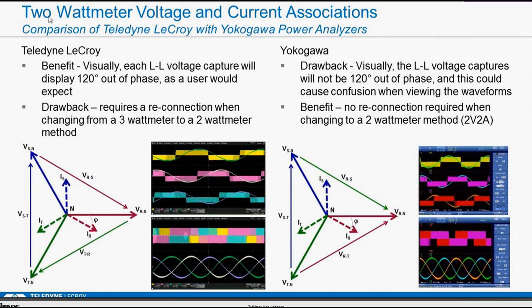One thing that gets confusing is, and this isn't bad, it's just the way it is. Typically, a power analyzer, I think, is always in a two wattmeter mode, and so it can be a little confusing that even if you're hooking up three voltages and three currents, they're probably still going to make calculations in a two wattmeter method. So the connection methodology they ask you to employ when you're connecting your voltages might be a little counterintuitive. The numbers come out correct, but the waveforms you might see on any screen display they provide might be a little weird.